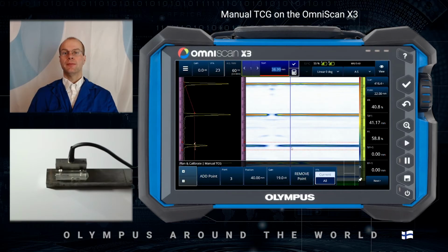Okay, here we are. Then I press the gain button on the top of the screen. I will press the auto 80% and record the gain value, 5.8 dB. So this is the additional gain which is needed for this signal to be at 80% full screen height.